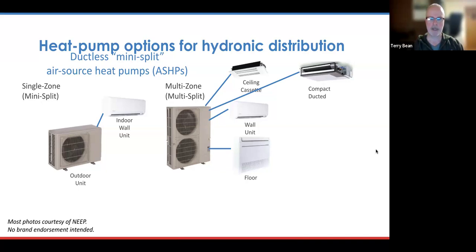It is limited. It basically comes in two sizes, one that can treat two areas and one that can treat up to four. And it's also limited in terms of how long of a run the flexible hose can make. But it does offer some advantages relative to the non-ducted solutions in smaller confined spaces where even the smallest wall-mounted mini split might be oversized. So a lot of times a nice line to walk between the advantages of both types is to have maybe a non-ducted unit or two in some larger open areas that communicate from area to area, and then maybe in tandem with that, some sort of compact ducted solution for a smaller cluster of rooms that's maybe adjacent to that. So combining those on one outdoor unit is possible. It's called a mixed use system, and those are available.